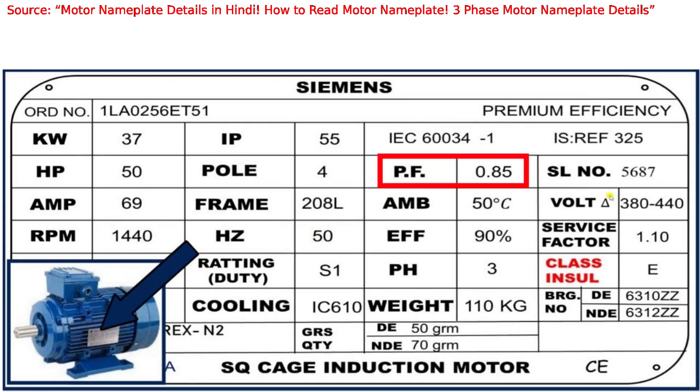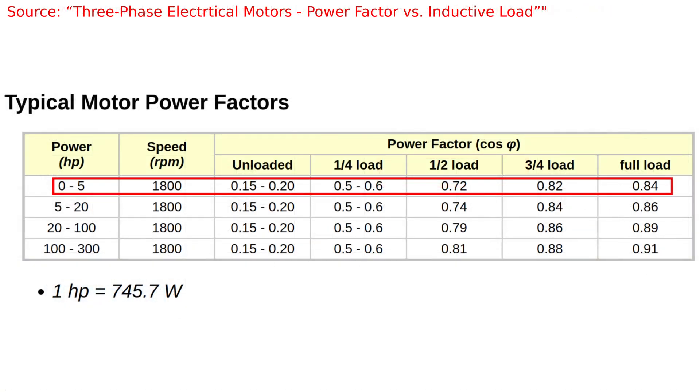Earlier, I said that the typical power factor of a motor this size is around 0.8. This parameter is written on the nameplate of induction motors, and the value written is the power factor when the motor is at full load. However, the power factor isn't a constant parameter. It changes with the load. So, if I'm loading my motor with half its full load, its power factor will decrease.